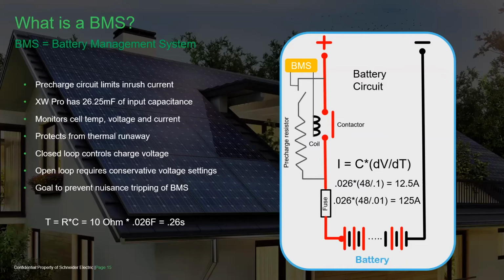When you multiply that capacitance out, at a tenth of a second after first closing the switch, you're looking at 12.5 amps. At a hundredth of a second, it's 125 amps. Looking at milliseconds on a scope, you can see that instantaneous value can climb close to 1,000 amps, but it doesn't blow a fuse, because a fuse requires a longer period of time for that current to be above its rating.